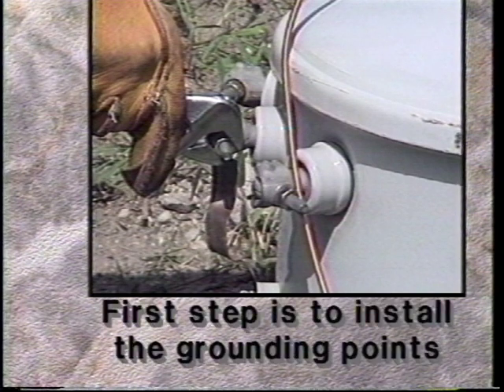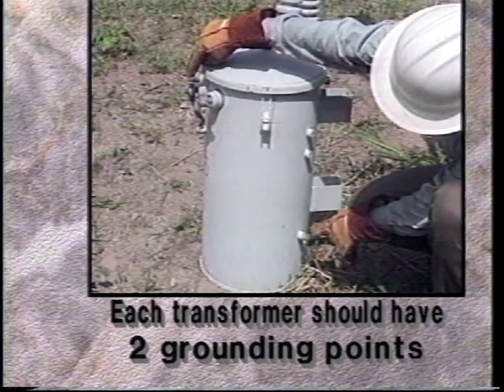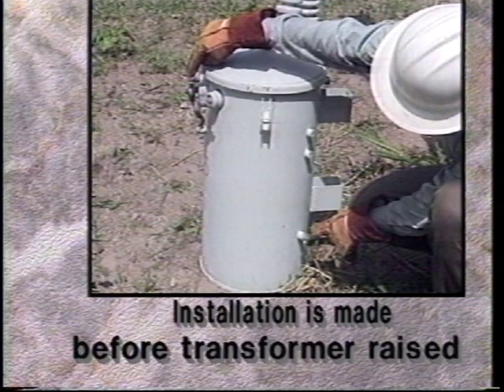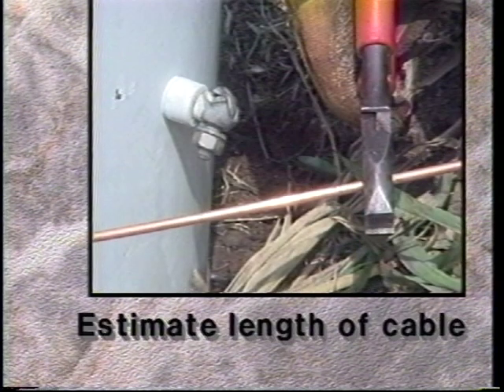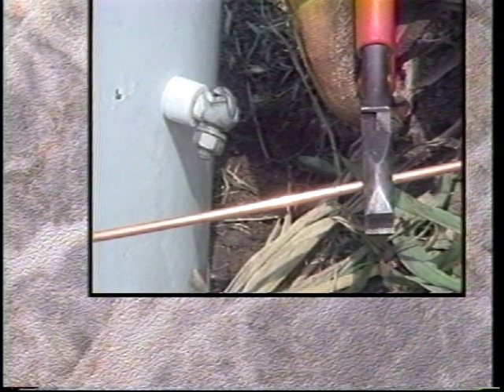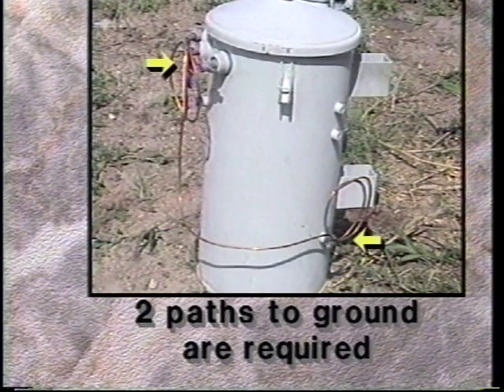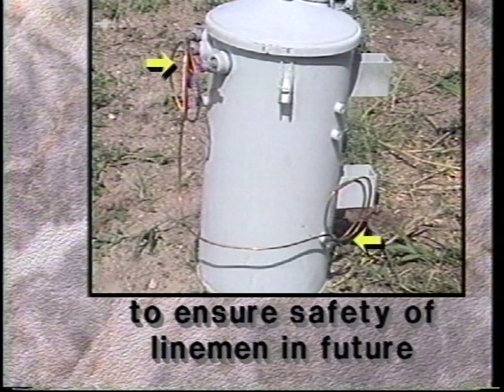Once on site, the lineman or his assistant should prepare the transformer for mounting. The first step is to install the grounding points. Each transformer should have 2 grounding points, which are identified by the lineman. The installation is made before the transformer is raised. Estimate the length of cable that will be needed to carry out the grounding installation. 2 paths to ground are required to ensure the safety of linemen in the future.